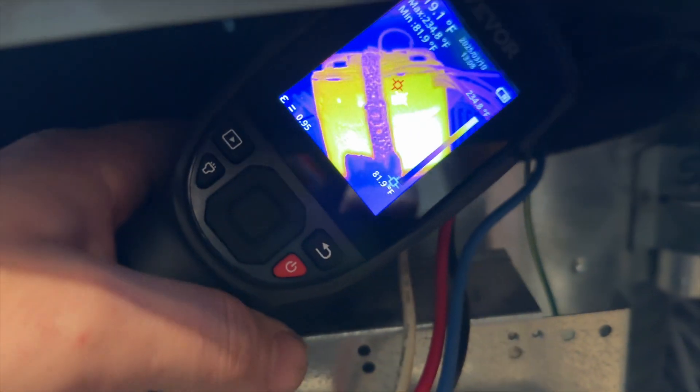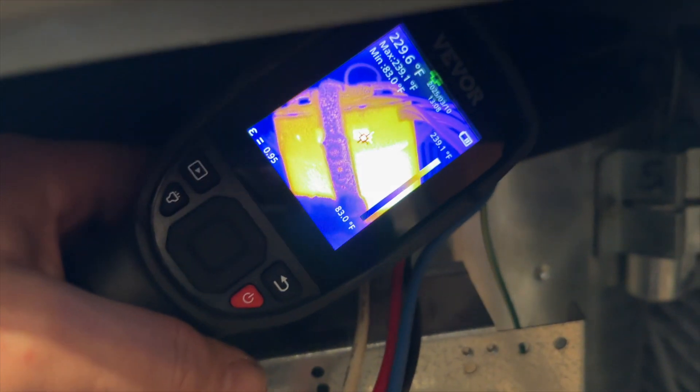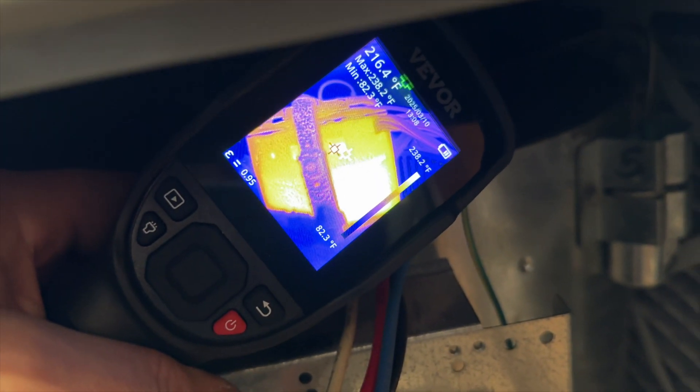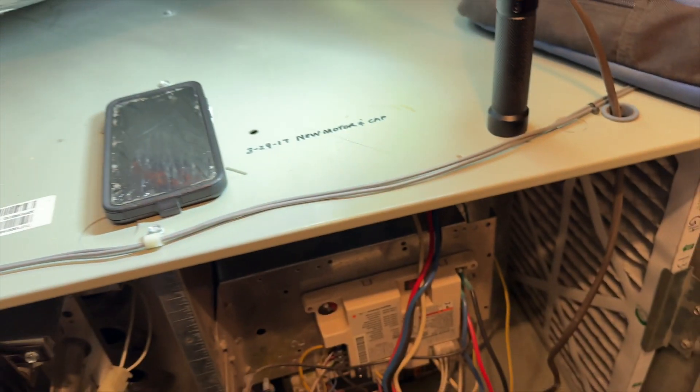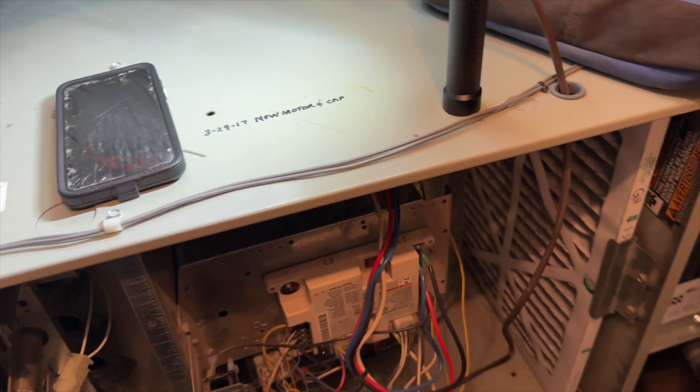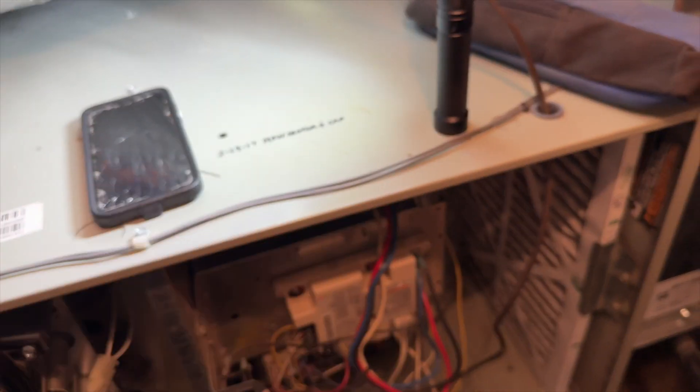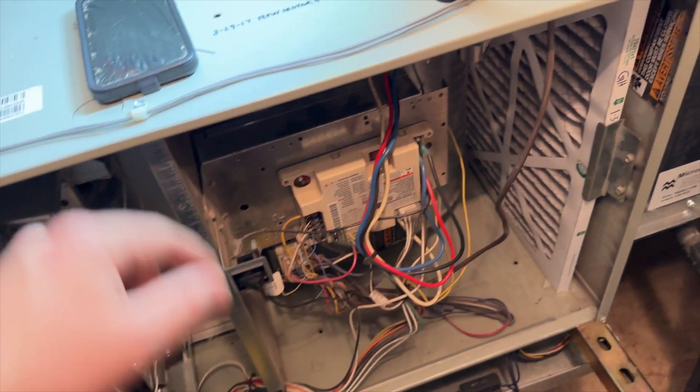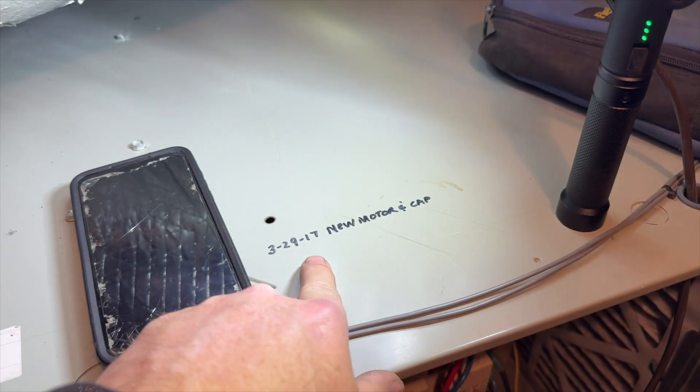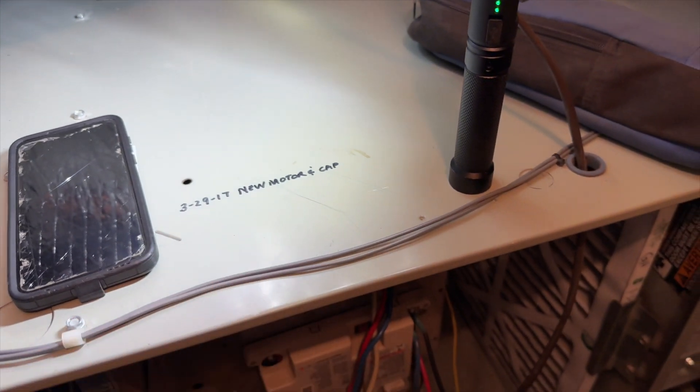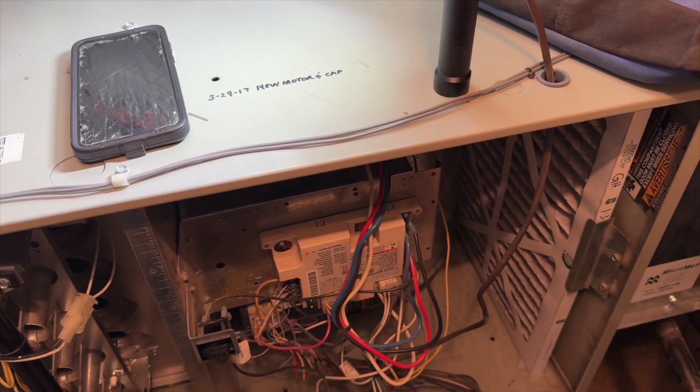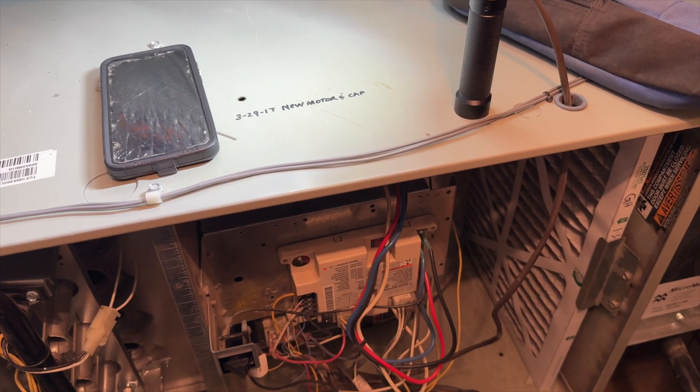Yep, that's where the blower is. Check that out, she is hot, 215 degrees. I can smell the electrical burning, so looks like the blower went out. It's been replaced in 2017, so we're going with blower number three. Third time's a charm hopefully.